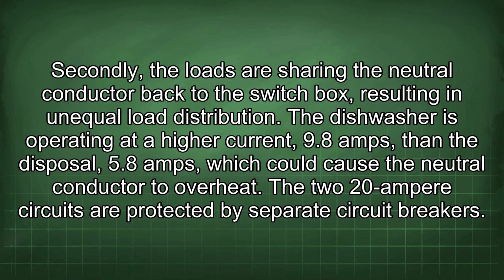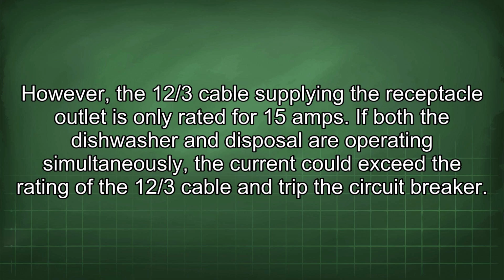The dishwasher is operating at a higher current, 9.8 amps, than the disposal, 5.8 amps, which could cause the neutral conductor to overheat. The 20 ampere circuits are protected by separate circuit breakers. However, the 12/3 cable supplying the receptacle outlet is only rated for 15 amps.